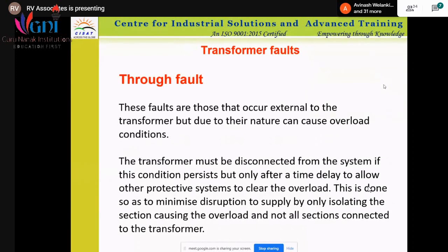Then there are through faults. Through faults means faults outside of the transformer, like faults in maybe a substation area. In the substation area, outside the transformer, there are power system lines. So faults in the power system line, which lead to the failure of the transformer, are called through faults. Because of the fault in the external system, there will be a rise in voltage or maybe current. It can be an overload condition for the transformer, which will lead to the fault.